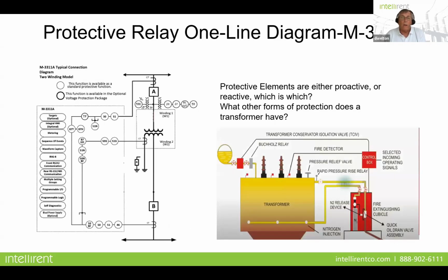If we look at the one-line protective diagram, this is the one from Beckwith Electric. You'll see here that you have various instrument transformers. You have CTs on both sides of the transformer to measure current going in and coming out. You've got PTs if you have voltage elements enabled as well, which many of them do, to protect from overvoltage conditions and things like volts per hertz.